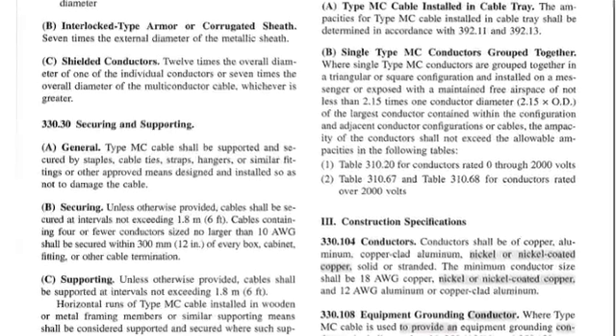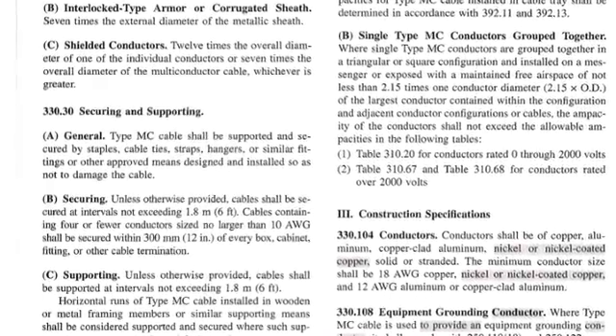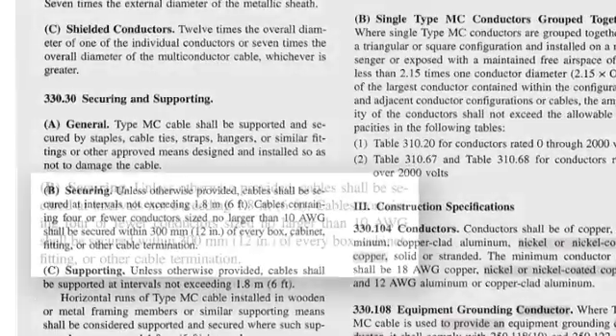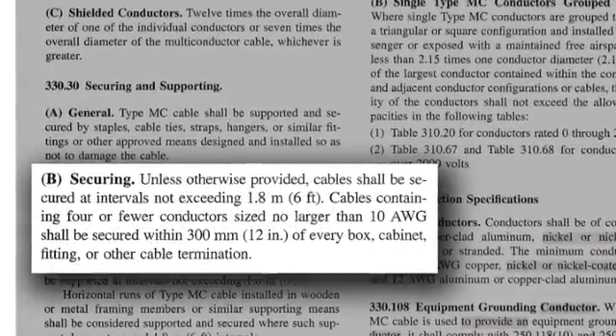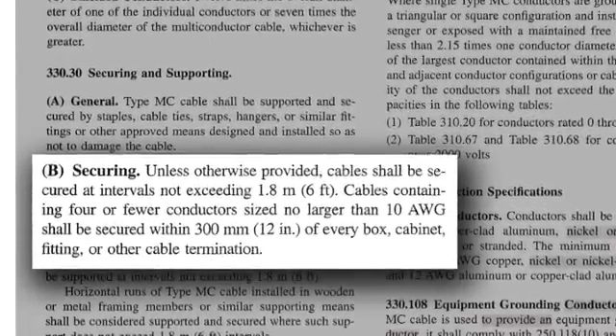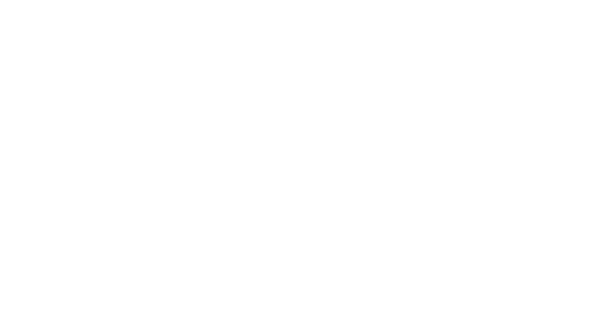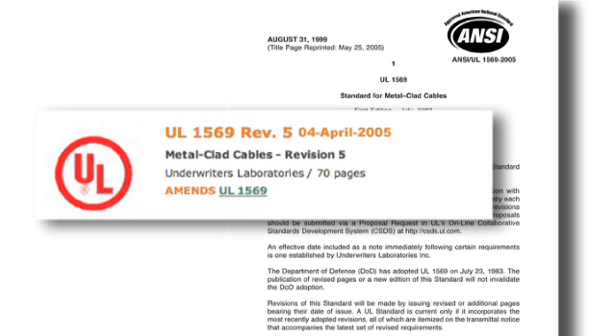When installing MC feeder in a vertical application, the National Electric Code Section 330.30B requires that the overall MC assembly be secured every six feet. All MC cables must also meet Underwriters Laboratories UL1569, the UL standard for safety of metal clad cables.